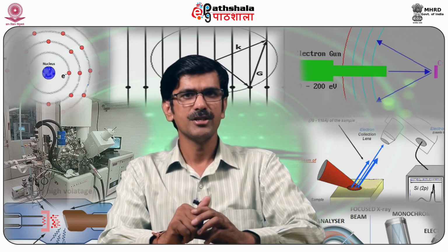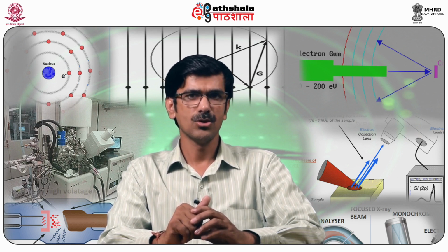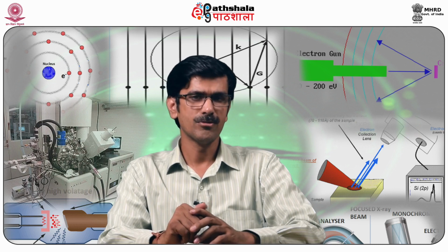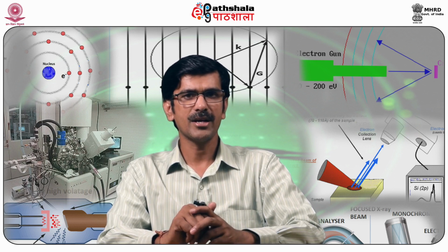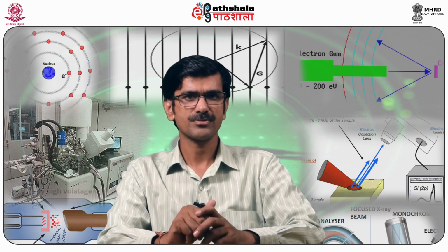The monochromator efficiently removes Rayleigh scattering and stray light. This serves as dispersing element for the incoming radiation. So, to obtain high resolution, conventional Raman system uses a detector photomultiplier tube, generally known as PMT tube. Apart from krypton and argon ion lasers, which are used in routine sample excitation, UV lasers have also been used.